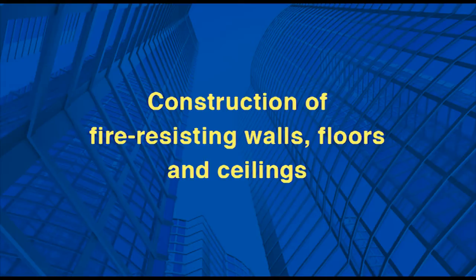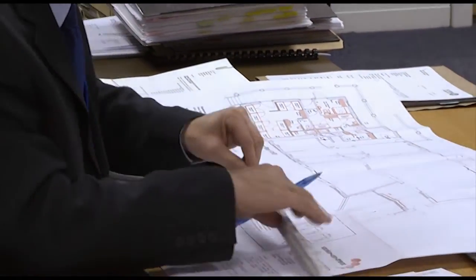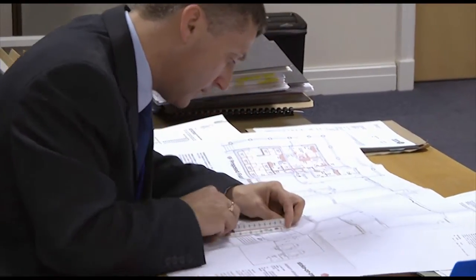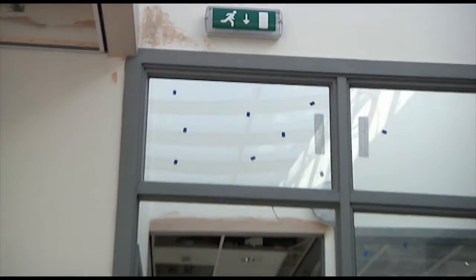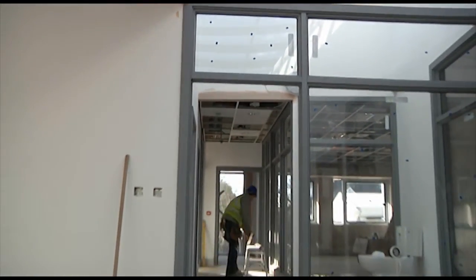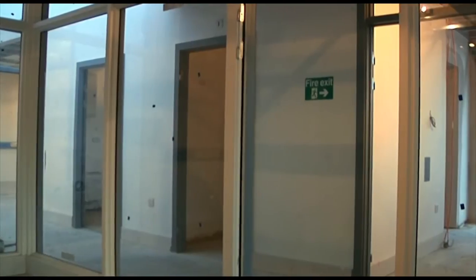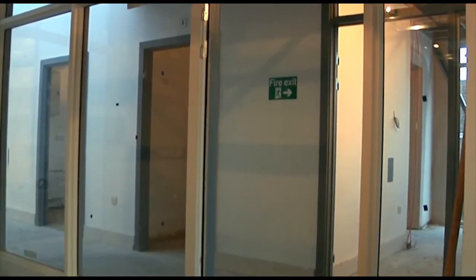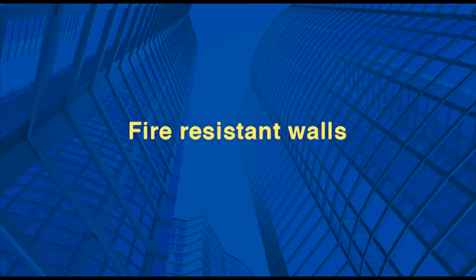The building control process for new buildings generally ensures that escape routes and compartmentation meet the required fire-resisting standards, so they should not require extensive evaluation. However, when changes to internal layouts alter the positions of fire-resisting walls and partitions, assessors will need to verify that escape route safety and compartmentation integrity have not been adversely affected. For example, any new construction must not breach compartments or substantially increase escape route distances.